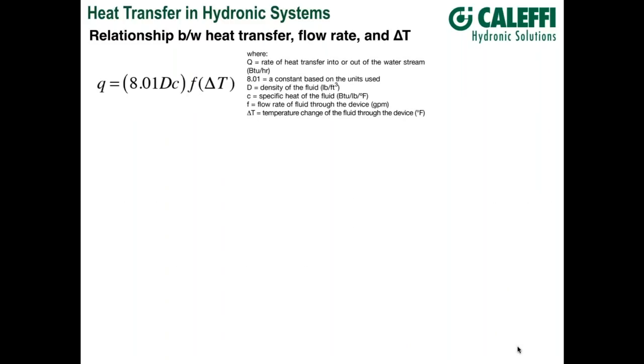Now let's get into something specific for hydronics. This very commonly used equation relates rate of heat transfer to flow rate of a fluid and temperature change in that fluid. The factor 8.01 makes the units consistent. D is the density of the fluid and C is the specific heat — when we change from water to antifreeze, D and C change. These are fluid properties that not only change with the fluid type but also with the temperature of the fluid. We can put measured values of flow rate, temperature change, and fluid type into this formula to calculate the resulting rate of heat transfer.